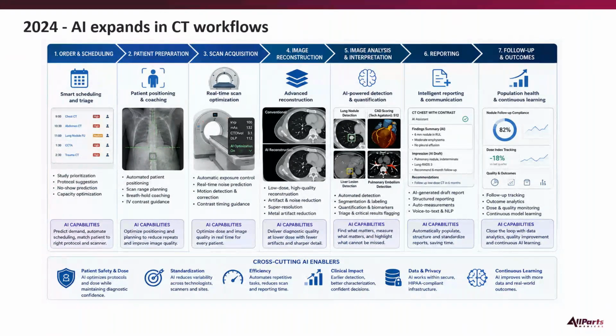Now with 3D cameras mounted above the patient table, as they load the patient on the table, the 3D camera can say, oh, we're doing a head study, so it automatically can size that patient's head. Instead of overscanning the patient, aka introducing more dose, now that range is limited. Also, if the patient is longer or shorter, the camera picks that up when you're doing chest and those kinds of things, to help define the protocol, the ranges that we're going to be scanning with. So those are enhancements using a camera and modifying the front end protocols defined by that OEM on that product, to help the tech better create a protocol that's going to be useful for that scan for that patient.